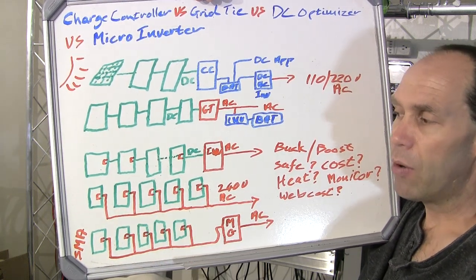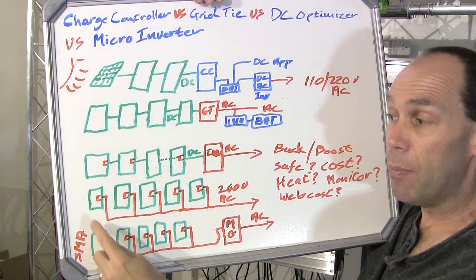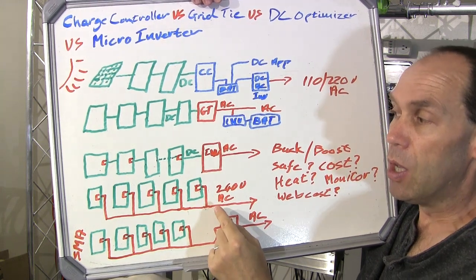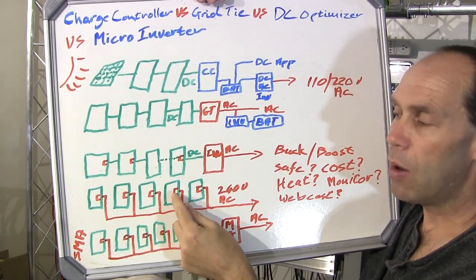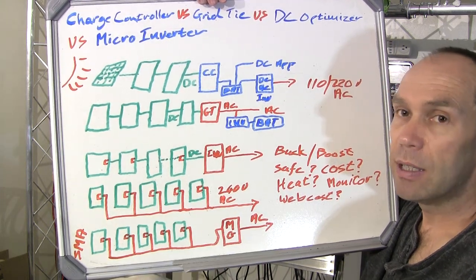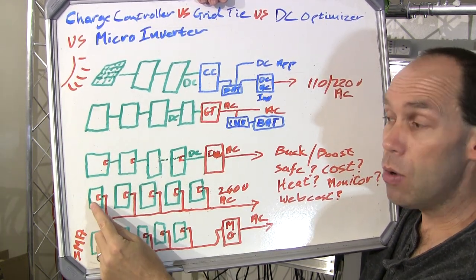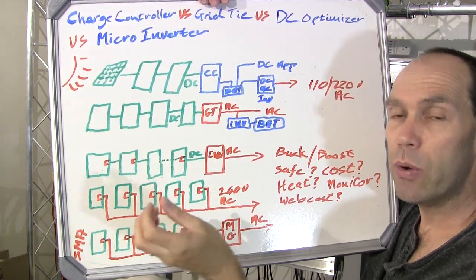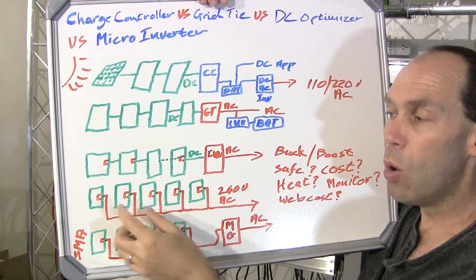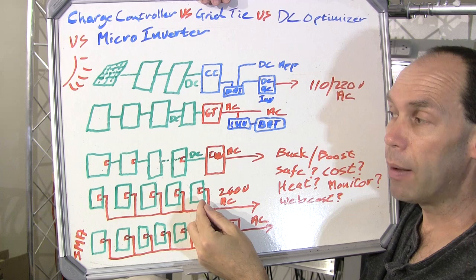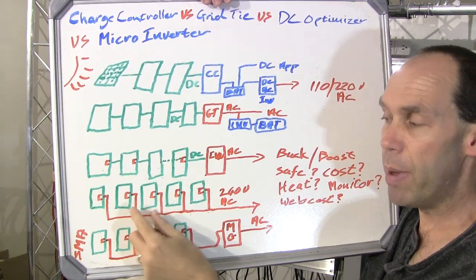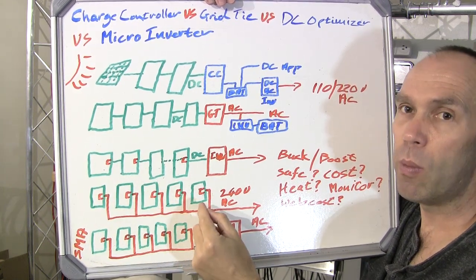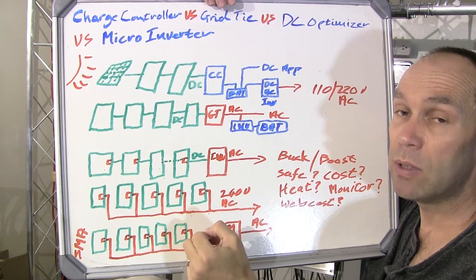The next solution is micro inverters. The beauty of micro inverters is that they are generally connected in parallel — so if a solar panel or micro inverter goes down, the rest of the system is still up and running. Each will have its own MPPT, so each panel is optimized for its varying conditions whether it's shaded or in full sun. Many of these systems also have a monitor which allows you to see how each panel is performing and can highlight an issue if one isn't performing well.